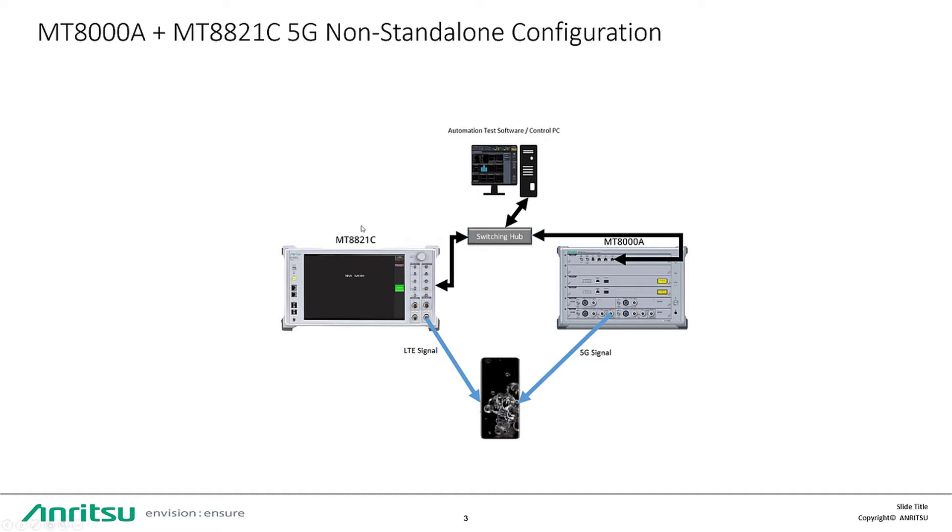On the left, the MT-8821 generates the LTE signal, and on the right, the MT-8000A generates the 5G signal. Both signals can be either conducted or radiated onto the device that's being tested.